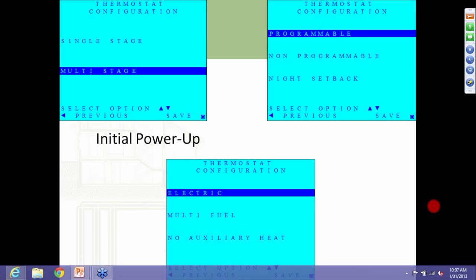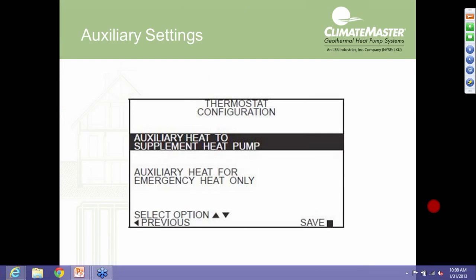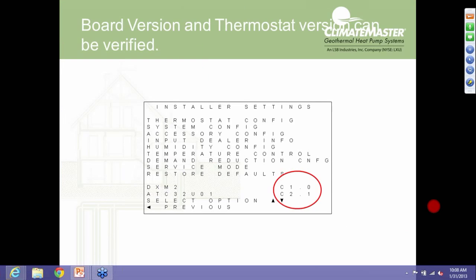And then we also need to configure whether we're going to have any kind of auxiliary heat. So electric being, again, our internal electric auxiliary heat pack. Multi-fuel, again, on our splits if we're doing a dual fuel application. And then no auxiliary heat in some cases where maybe down in the deep south we don't have any auxiliary heat installed in the heat pump. And then the next menu after auxiliary heat is how do we want to control that auxiliary heat pack? Do we want it to be able to supplement the heat pump, or do we want it only for emergency heat purposes? So we have that option.